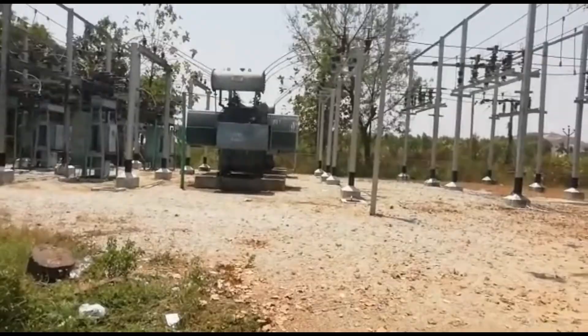Okay, now we'll move to the substations. Now we are in a 33 by 11 kV substation. From here only we will get power to our houses. This is a primary substation. From the 220 kilovolt by 132 kilovolt substation, we are getting power to this substation through transmission lines of 33 kilovolts. From this 33 kilovolt, it will go to the distribution systems of 11 kilovolt transformers.